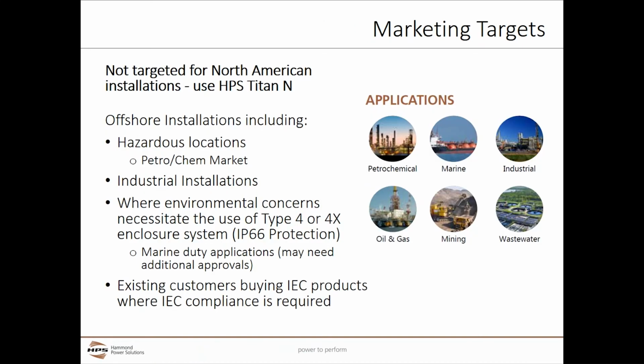So in terms of marketing targets, some of the industries covered by the range of IEC standards and the IECEx system include oil and gas refineries, offshore platform rigs and processing plants, automotive refueling stations or petrol gas stations, chemical processing plants, refueling hangars. So anywhere where there are hazardous substances present, or where there are environmental concerns that require Type 4 or 4X enclosure systems or IP66 protection. Also the marine duty applications. There might be some additional approvals that are required for marine duty, but please reach out to us, and we do have the ability to provide those additional approvals.